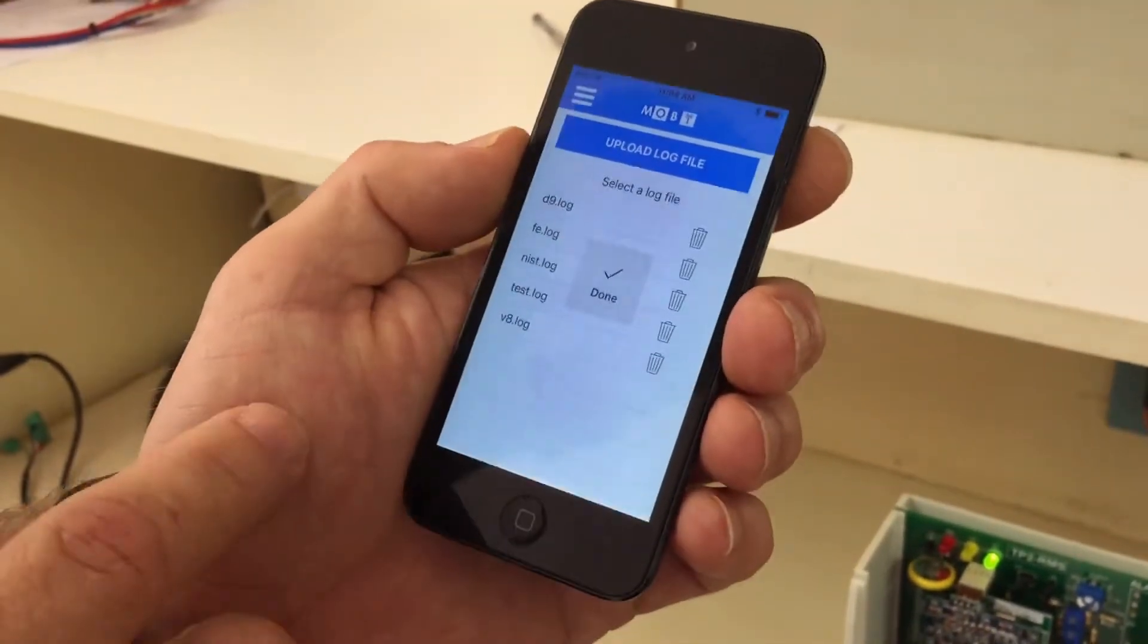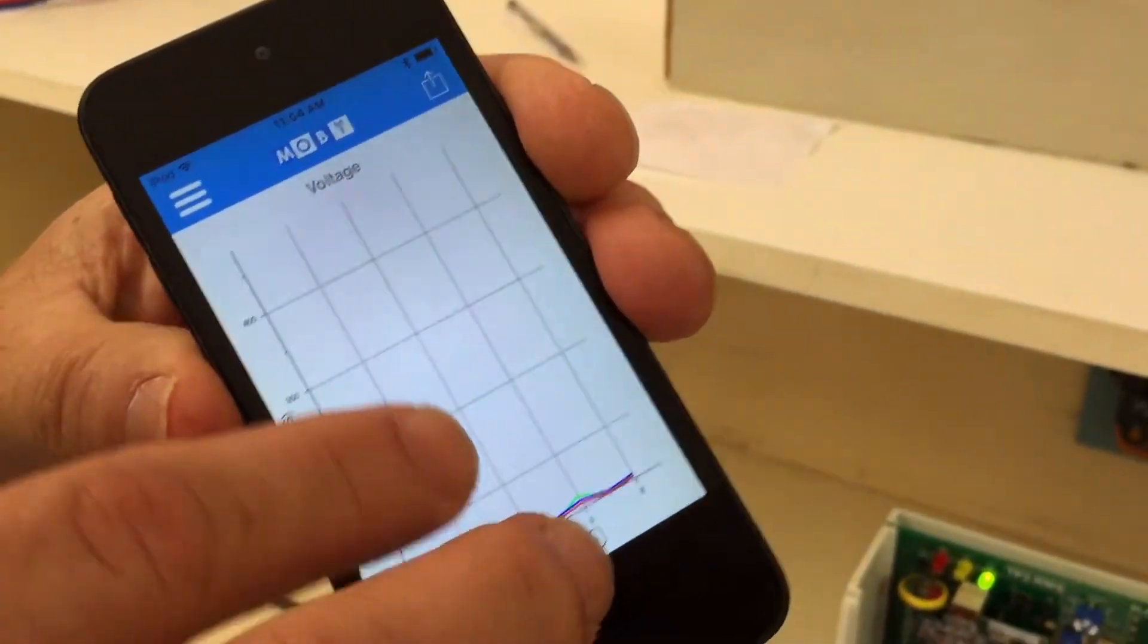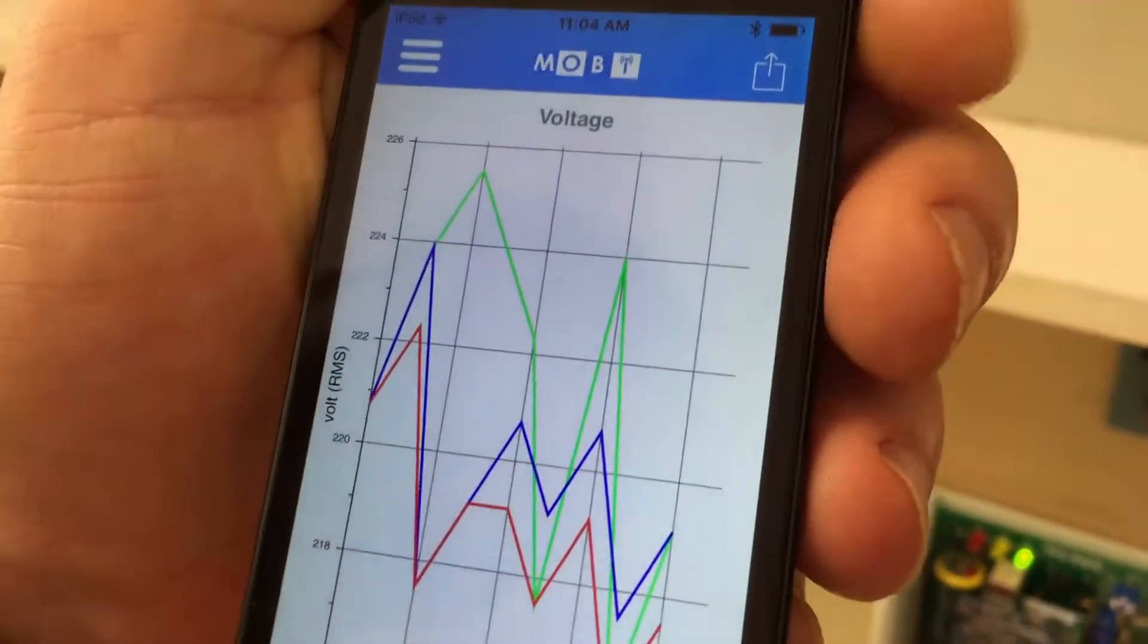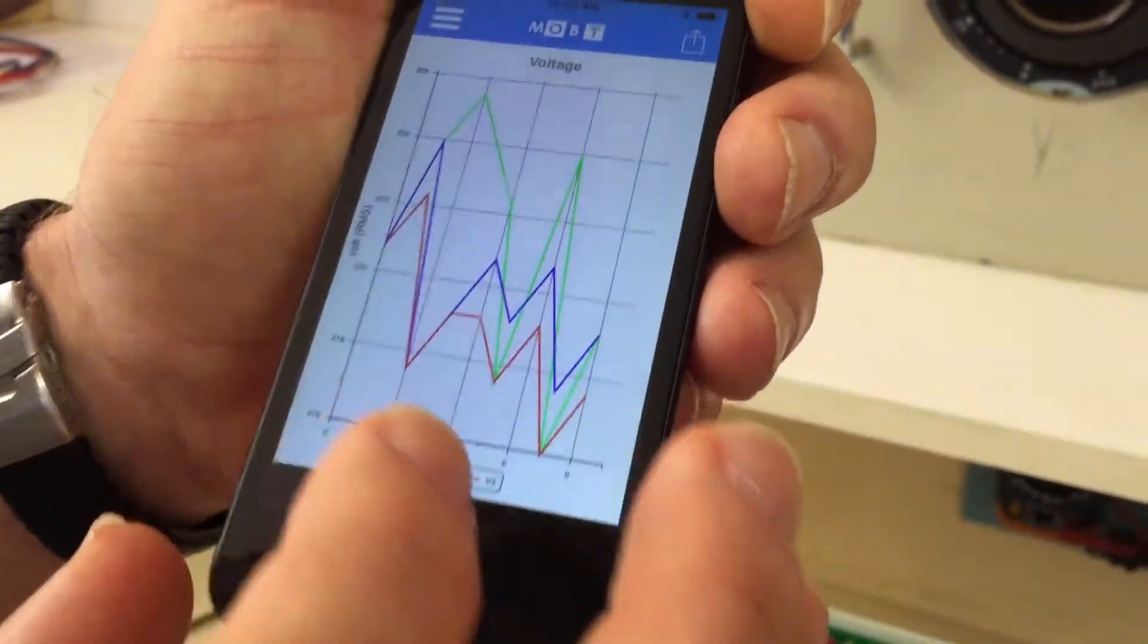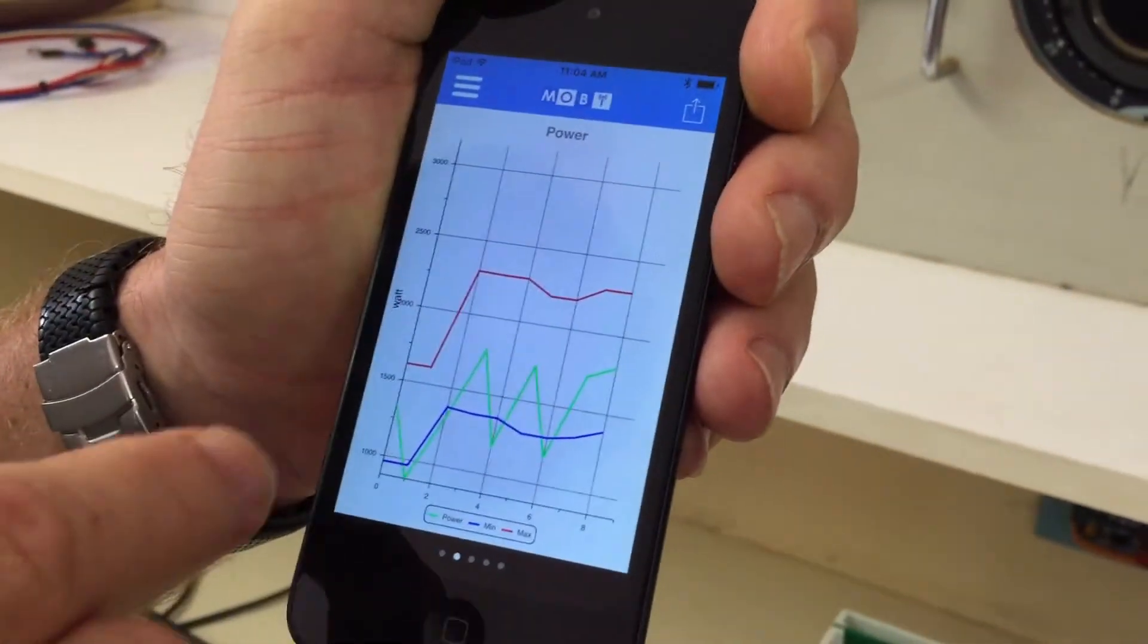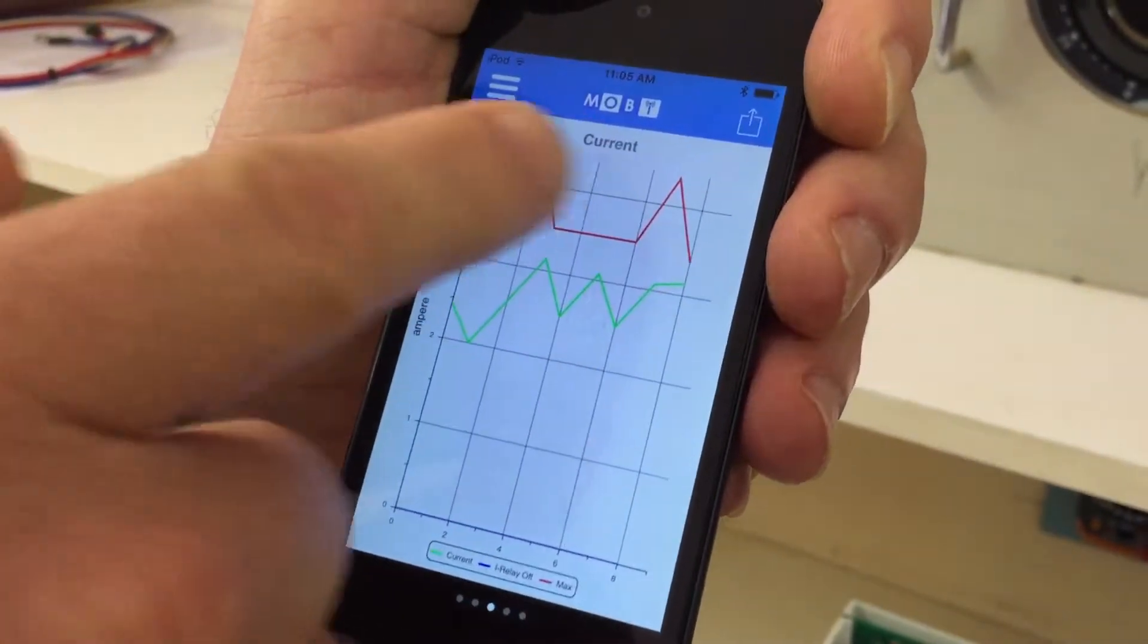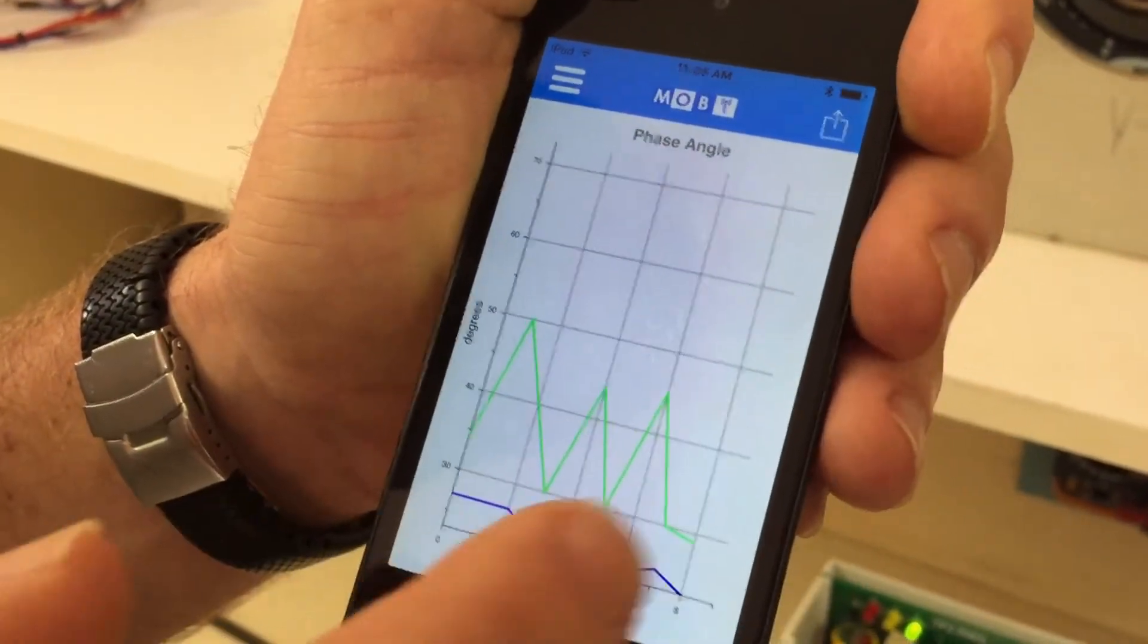Done. Okay. So, the file is created. Let's open it. And there you can see the voltage graph. And this can then be zoomed into. So, this also nicely demonstrates the zoom function. This is the voltages. And you can see the voltages is between 216 and 226 volts. There you can see your power graph. Red high limit. Blue low limit. Green consumed. So, there you can see one, two, three dryer and trips. Current, max current limit. The red current consumed in green. Phase Angle in green. The limit in blue.